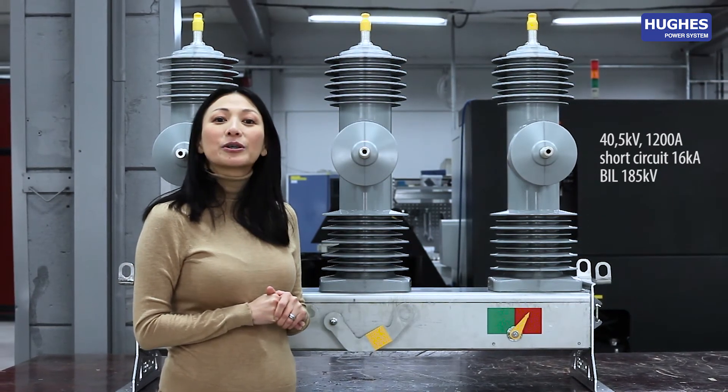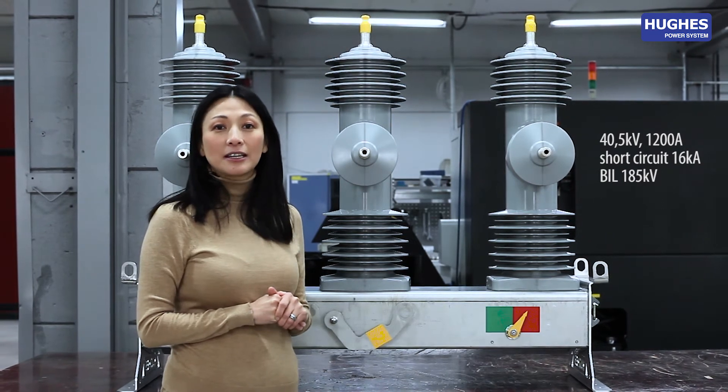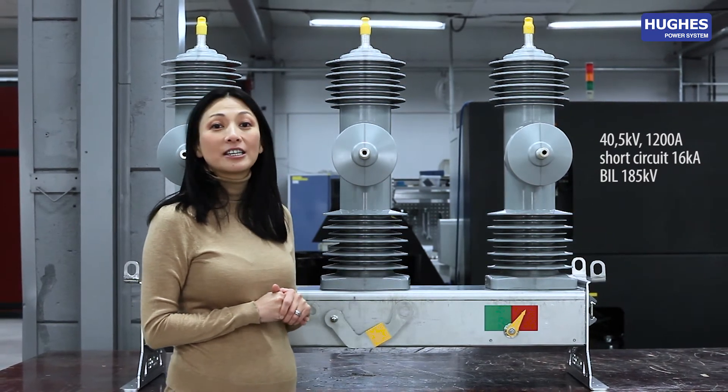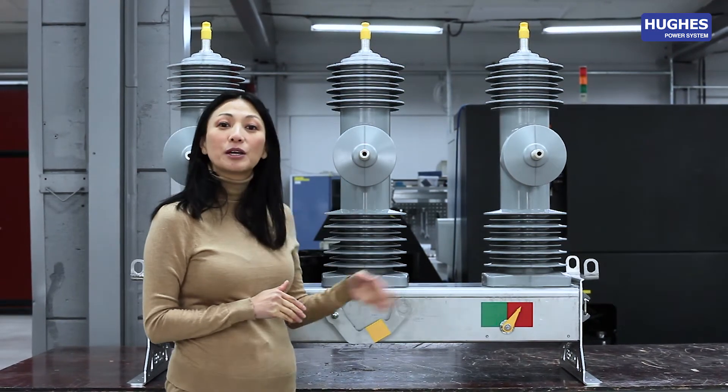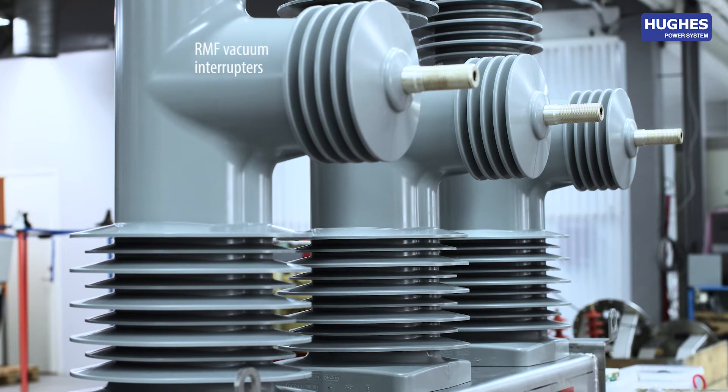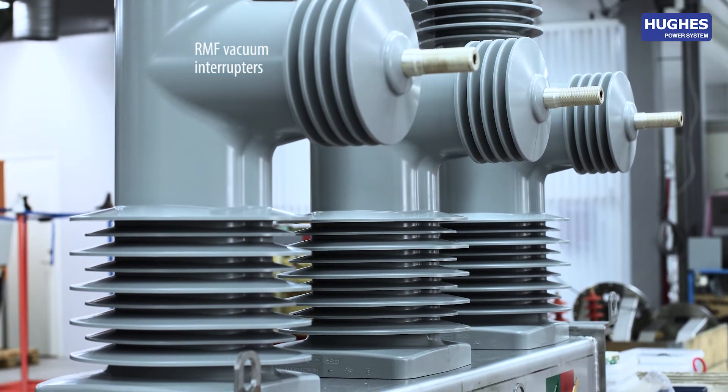The short circuit level is 16 kA with a basic insulation level of 185 kV. It's equipped with the latest technology of vacuum interrupters of RMF type.